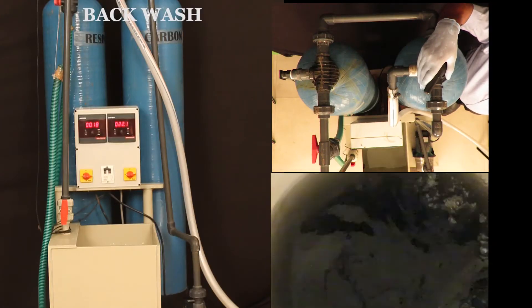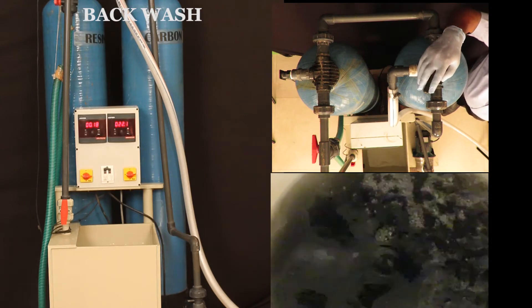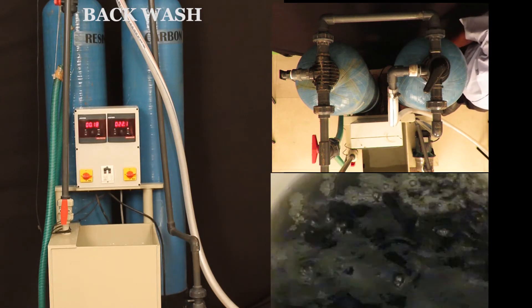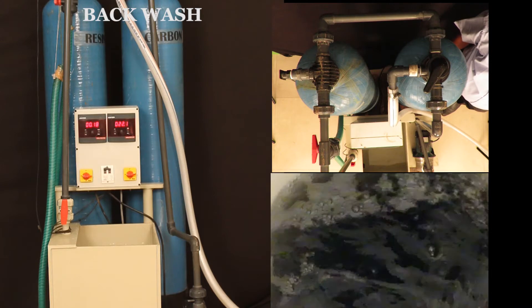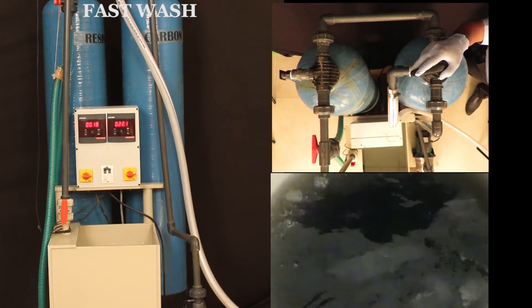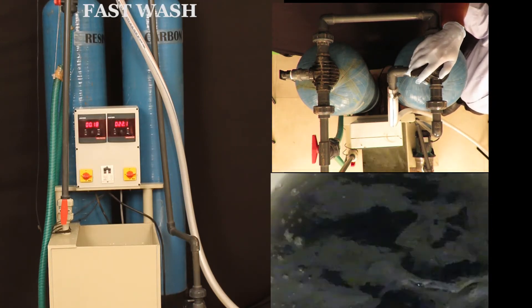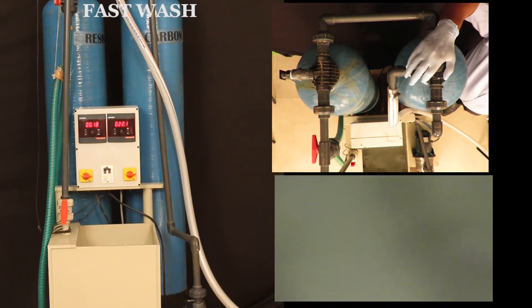Before starting the rinsing process, you should do a back wash for one and a half to two minutes, then fast wash for 30 seconds to one minute. Drain the water which is coming out from the hose pipe directly into a basin. As you can see in the video, water coming out from the pipe is quite oily and blackish. Repeat the process 8 to 10 times until the water comes out clean.